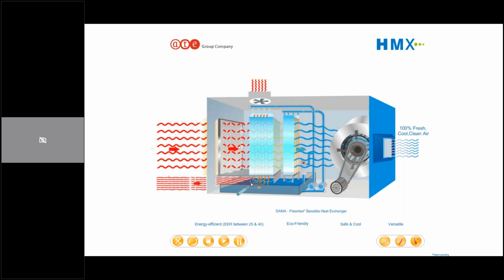But the first cost is there, and availability of waste steam matters, because if I require 1 kilowatt for a vapor compression system, I will need 3 kilowatt for a VAM for generating the same amount of refrigeration effect. So you require much higher energy. As long as it is waste energy, it makes sense. But if it's steam generated for the purpose, it doesn't work out. That's my perspective, and the analysis that I have done was for one project around 5 to 6 years back. Hope I have responded to your query suitably.